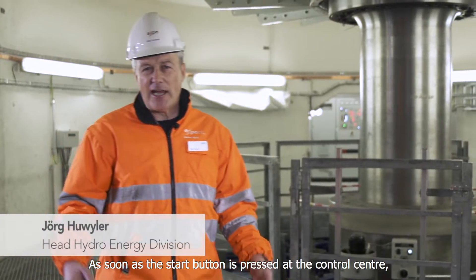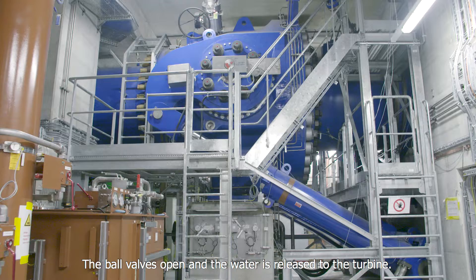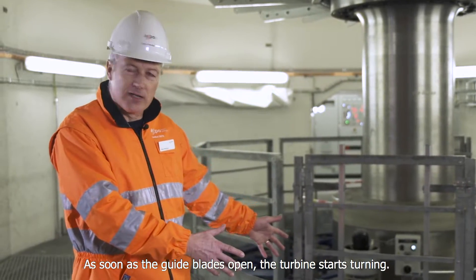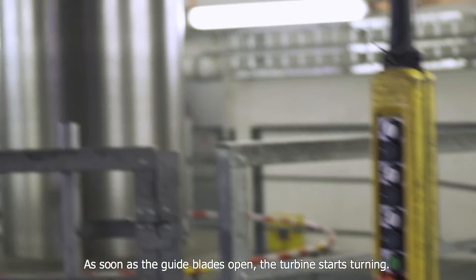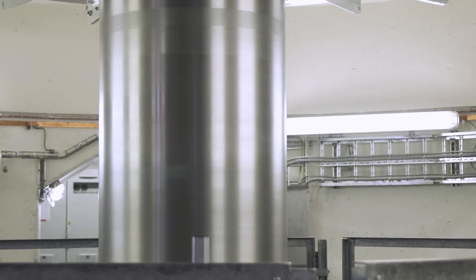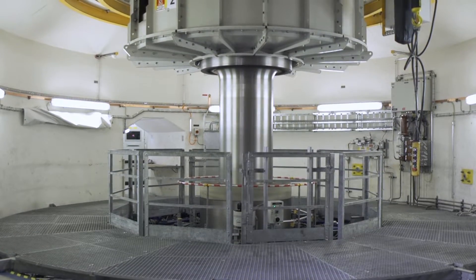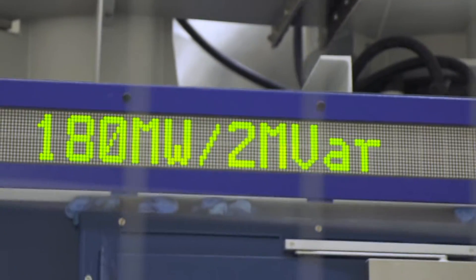As soon as the start button is pressed, all the auxiliary systems are running. Then we open the inlet valve, water reaches the turbine, and as soon as the guide blades open, the turbine begins to turn. The turbine rotates faster and faster until it reaches approximately 470 rotations per minute. At this speed, it is synchronised with the grid and delivers the power.